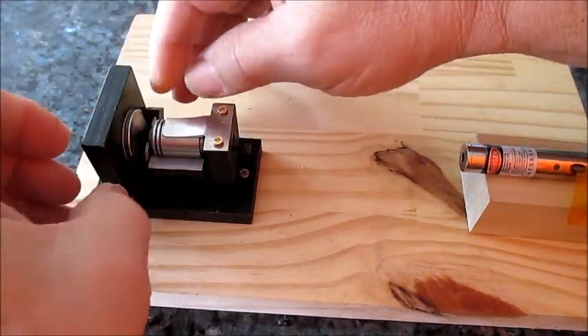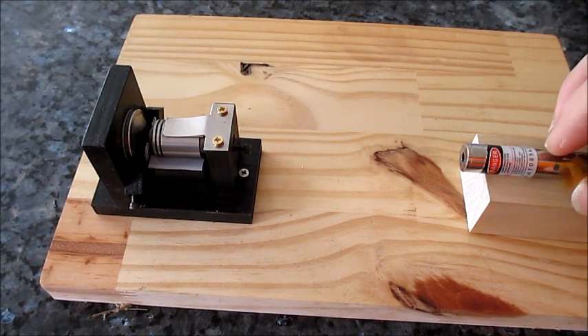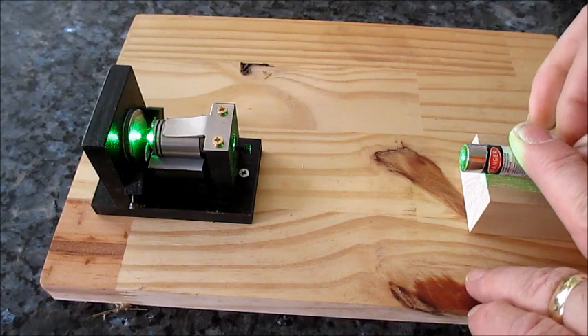Then I have my laser pointer. First thing we want to do is make sure that our laser is lined up with the microscope objective.